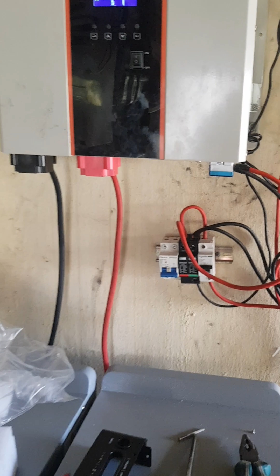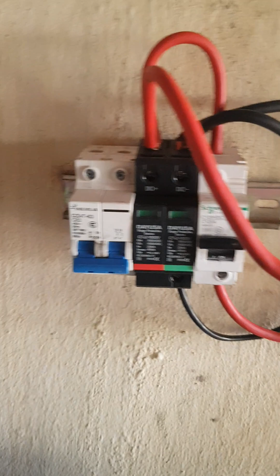An interesting thing to showcase is that these are well protected. Beside the inverter we have a DC circuit breaker, a surge protector, and we're also installing an AC circuit breaker and an AC surge protector. These aren't compulsory per se, but we want to be sure our installations are perfectly done and pose no danger.